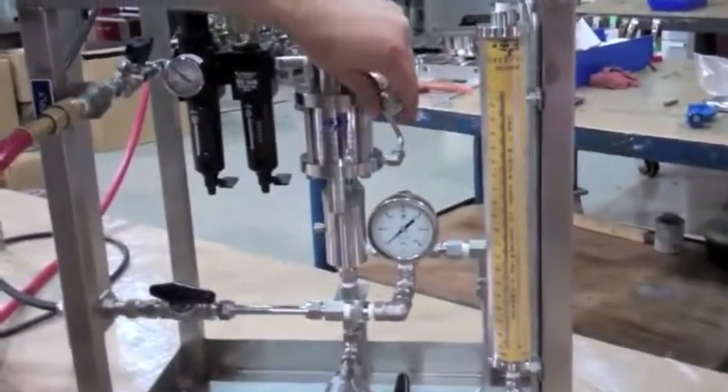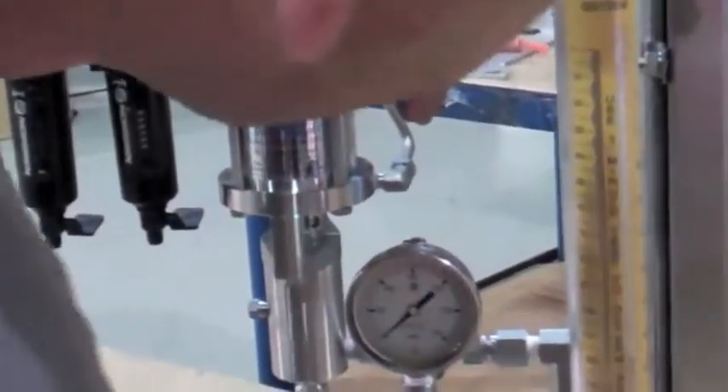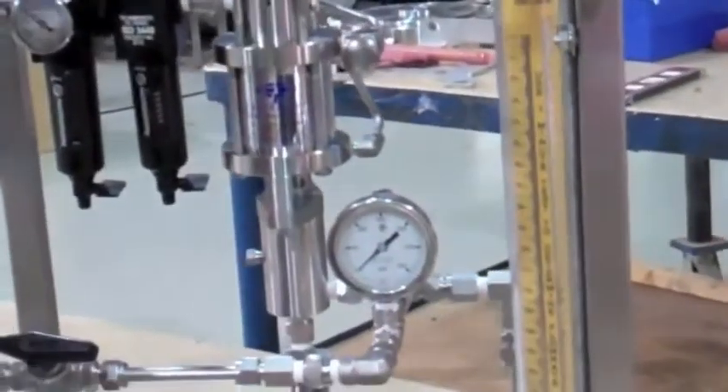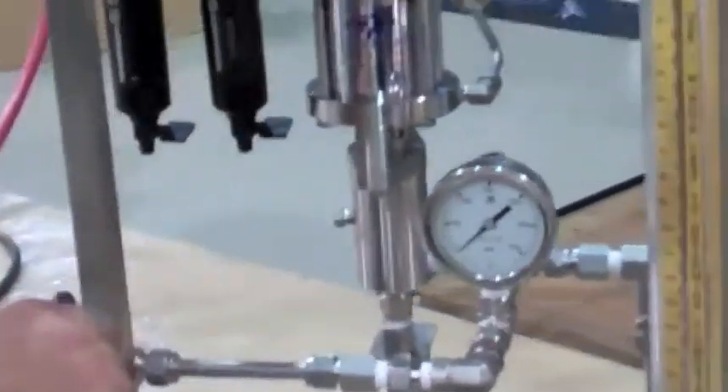Setting the PRV. First relieve system pressure. Using two 3/4 wrenches, hold the cap with one and use the other to loosen the lock nut. Speed up the pump by loosening the needle valve. Close the discharge line block valve to allow pressure to build up.